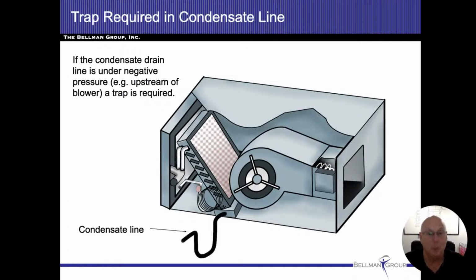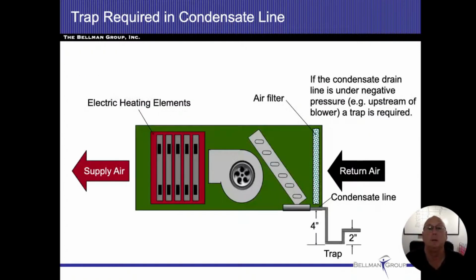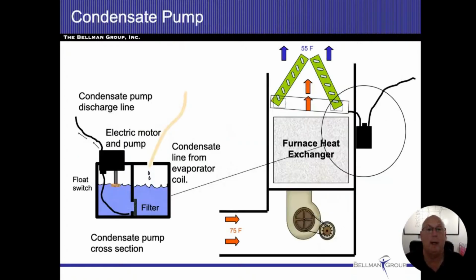I do want to stress, though, when we're dealing with gas forced air furnaces, which is what we mostly have in our area, the air conditioning coil goes after the heat exchanger and not before. In this drawing, we're showing before, but that's mostly because it's an electric furnace. And this is doing the same thing. So here they have the air filter, then the air conditioning coil, blower fan, and then the electric heating elements. This is very common with electric furnaces, and again, that has to be trapped.